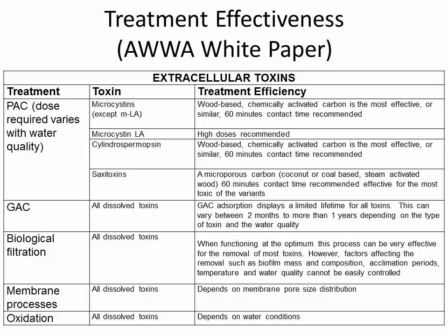Granular activated carbon, dissolved toxins. GAC adsorption displays a limited lifetime for all toxins, varying between 2 months to a year, depending on the type and the water quality. So in reality, powdered PAC is better than GAC, even though, of course, GAC is cheaper.